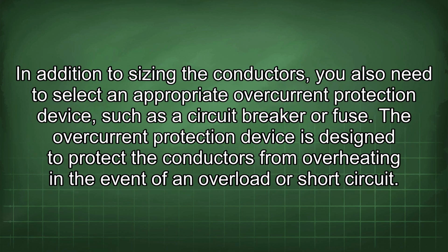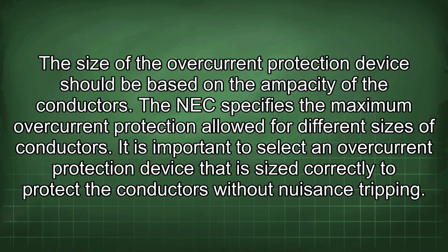In addition to sizing the conductors, you also need to select an appropriate overcurrent protection device, such as a circuit breaker or fuse. The overcurrent protection device is designed to protect the conductors from overheating in the event of an overload or short circuit. The size of the overcurrent protection device should be based on the ampacity of the conductors. The NEC specifies the maximum overcurrent protection allowed for different sizes of conductors. It is important to select an overcurrent protection device that is sized correctly to protect the conductors without nuisance tripping.